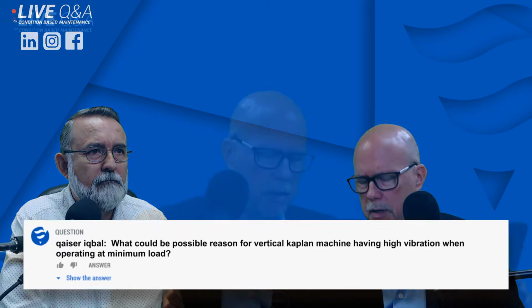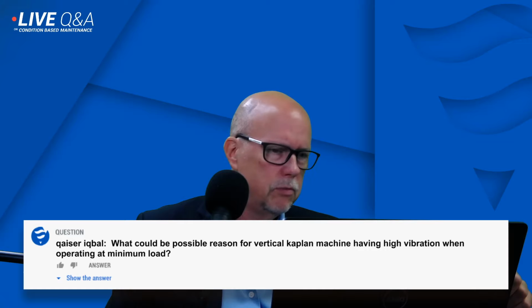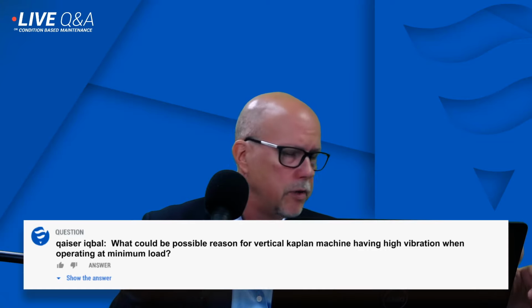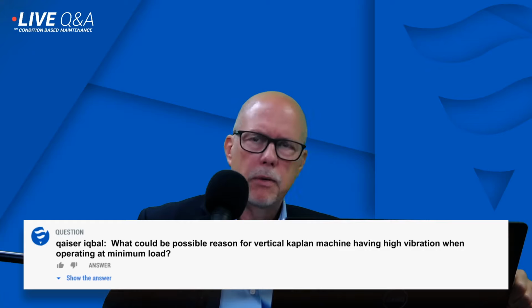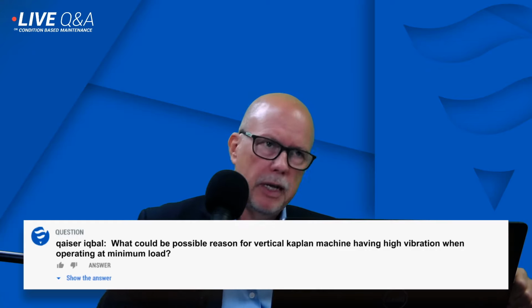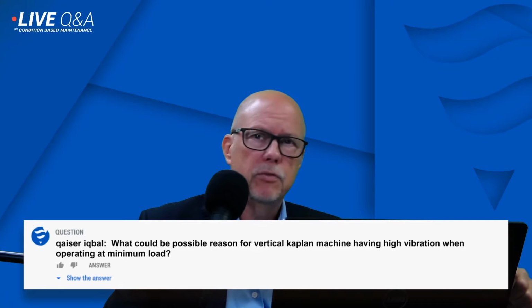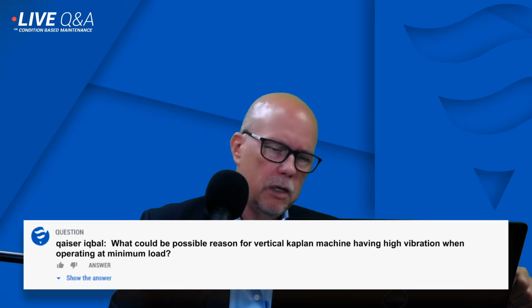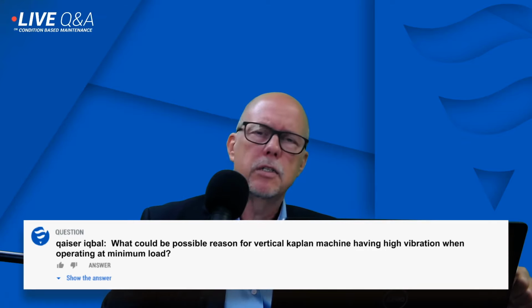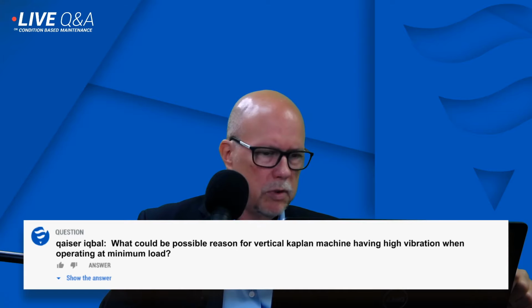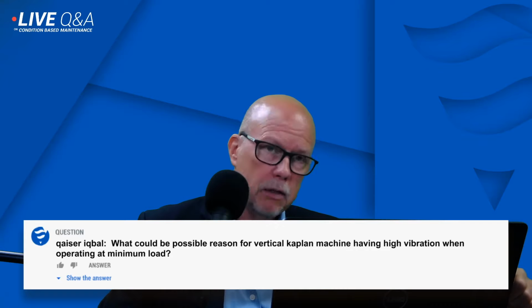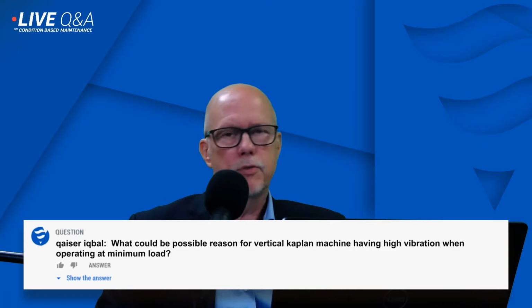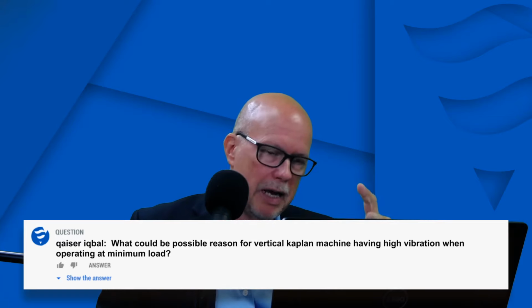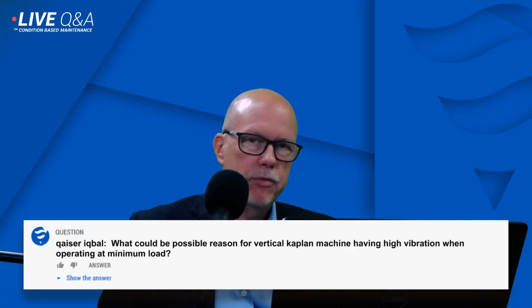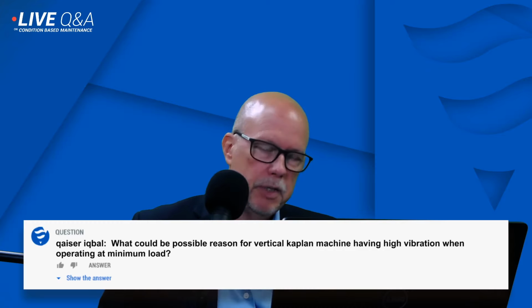That's more common. Minimum load, well, if minimum load, does that mean close to zero when you synchronize, or is it because you're running at, let's say, 25% load? Remember that, like I said, most hydro generators have a rough zone, and that can be anywhere from 15% to 50% load. And when you go into that zone, the unit becomes unstable. And usually what happens is you will see the unit will start skating, which is a subsynchronous frequency where the unit will have a high level of vibration at a frequency which is less than the actual rotating speed of the unit. We see that quite often.